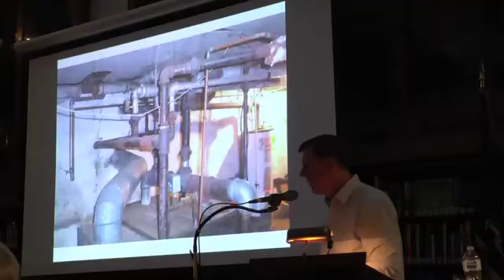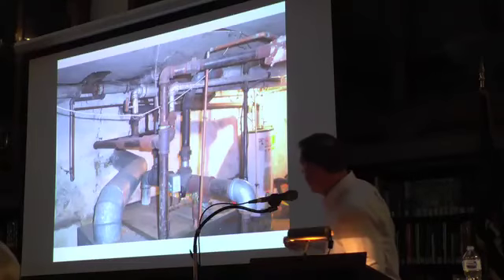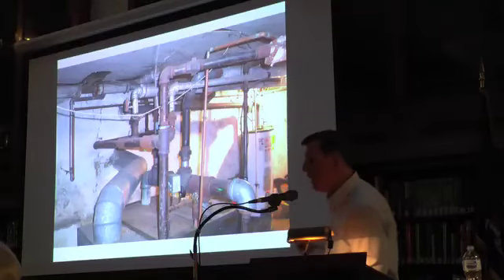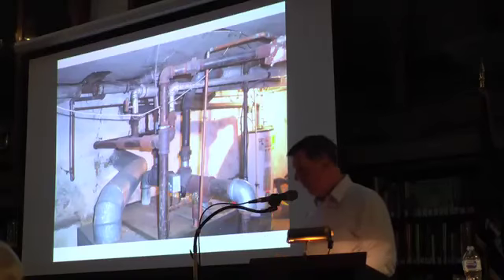But when you go out in the field, you see stuff like this. Like, where's my 24 inches? And notice how the steam comes out of here pulling the water. The water knows to go right as the steam is going left at 60 miles an hour, because you're going to put arrows on the inside of the pipe to direct the traffic and hope for the best.